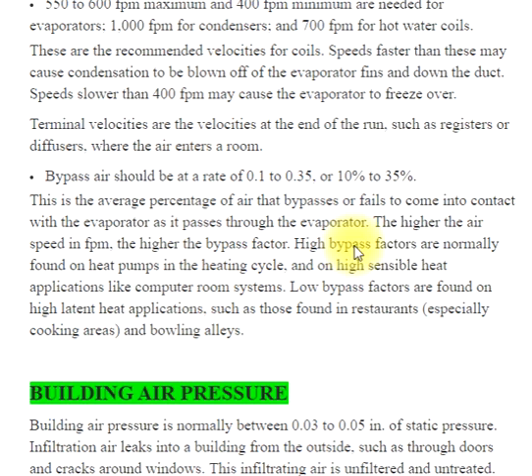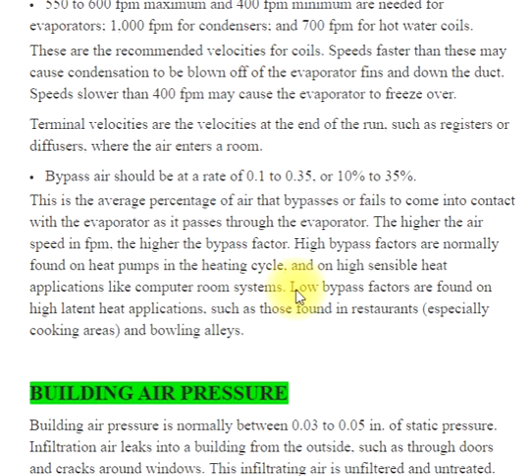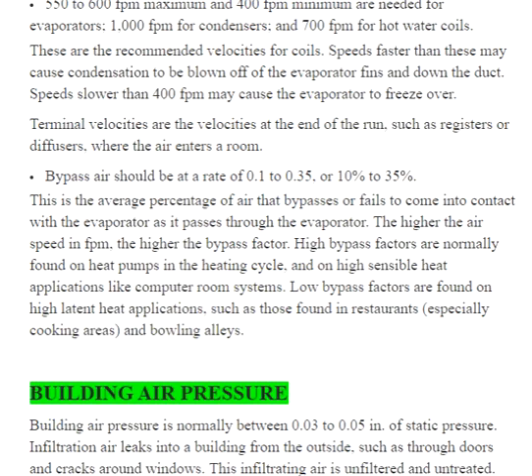High bypass factors are normally found on heat pumps in the heating cycle and on high sensible heat applications like computer room systems. Low bypass factors are found on high latent heat applications, such as those found in restaurants, especially cooking areas, and bowling alleys.